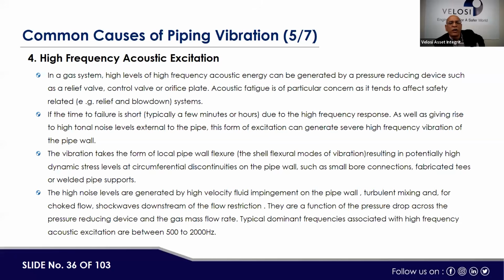Now, if the time to failure is short, typically a few minutes or hours, due to the high frequency response as well as giving rise to high tonal noise level external to the pipe in the form of acceleration, it can generate severe high frequency vibration in the pipe wall. The vibration takes the form of local pipe wall flexures and potentially high dynamic stress levels at the circumferential discontinuities. Normally, if the vibrations are high and the noise is on the higher side, and the frequency goes beyond the acceptable limit, then there is a potential for failure at the anchor location or at structural discontinuities like bends and tees. There could be high stress, and this may basically cause a failure.